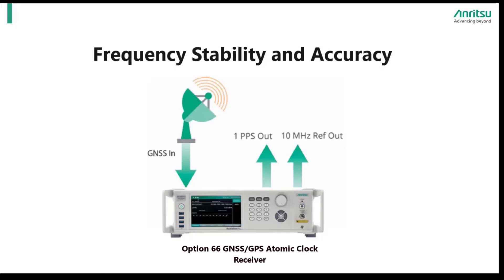Like Option 56, stability performance can be used to tie other signal generators through a 10 MHz reference or a 1 PPS output signal. To truly emphasize Rubidium's frequency stability and accuracy: currently none of the signal generators in the market offer a built-in option for atomic clock frequency stability and accuracy.